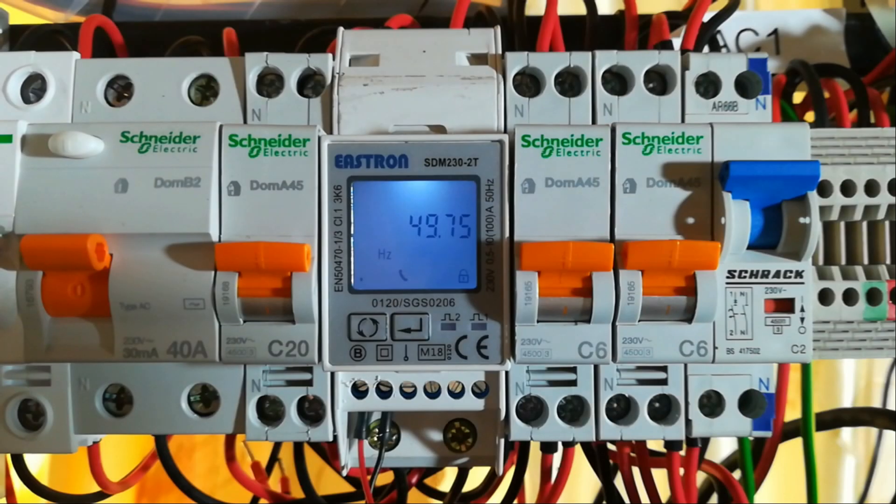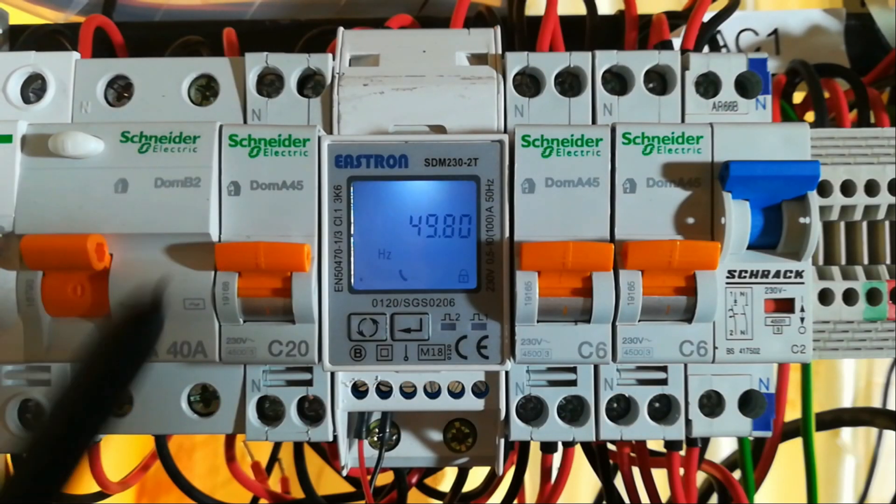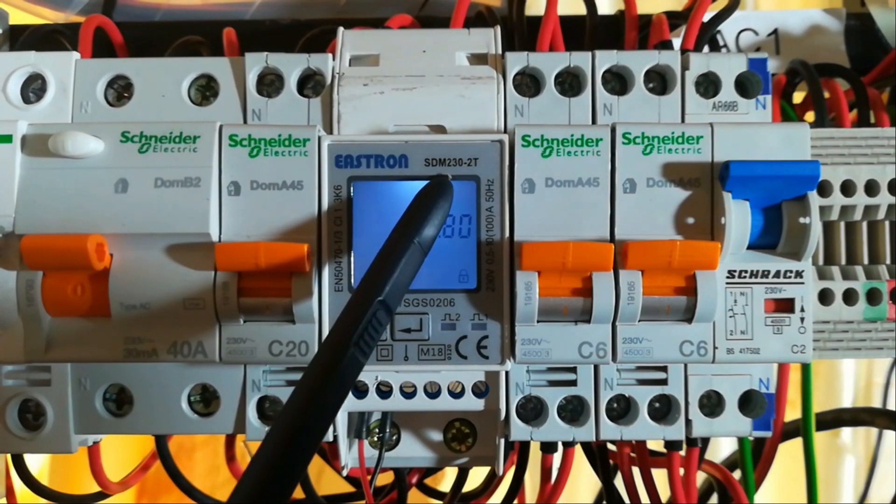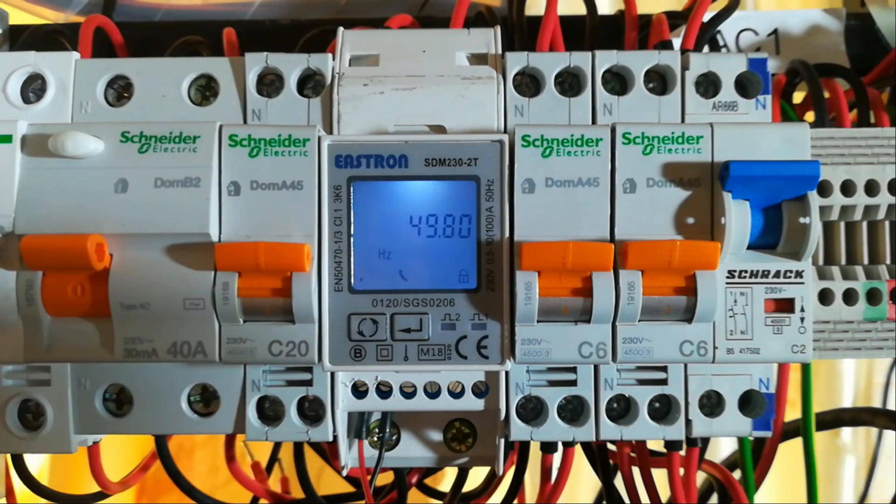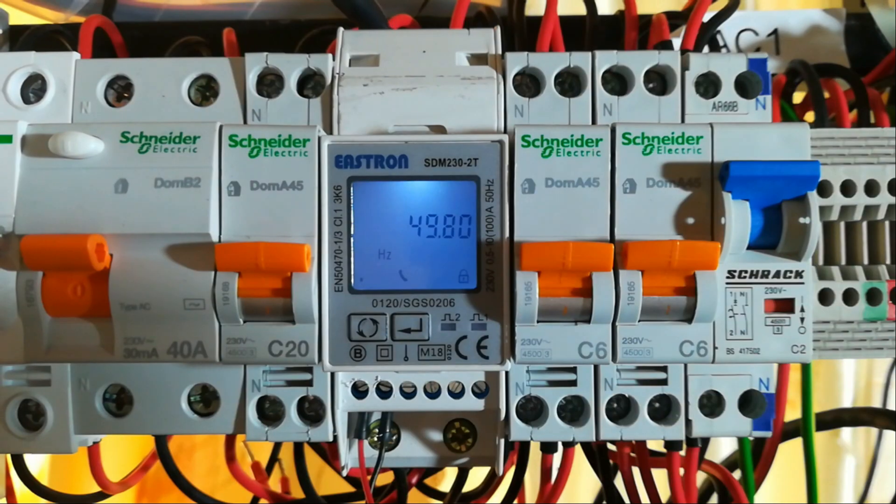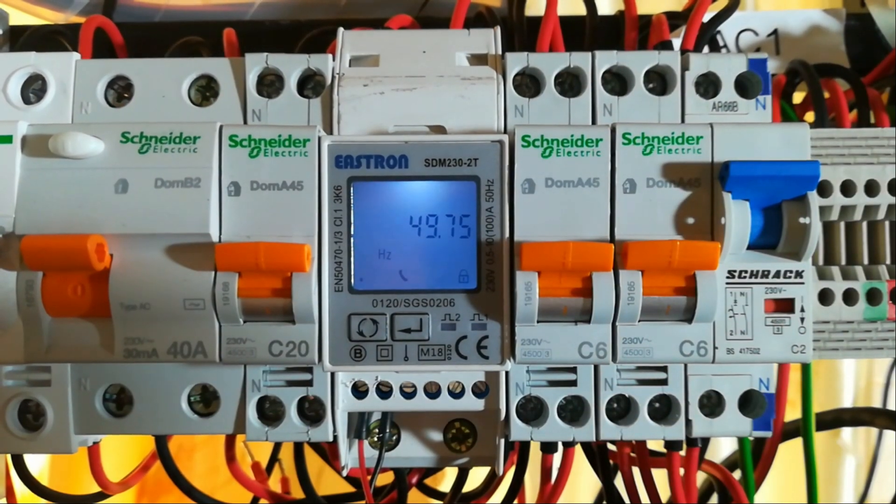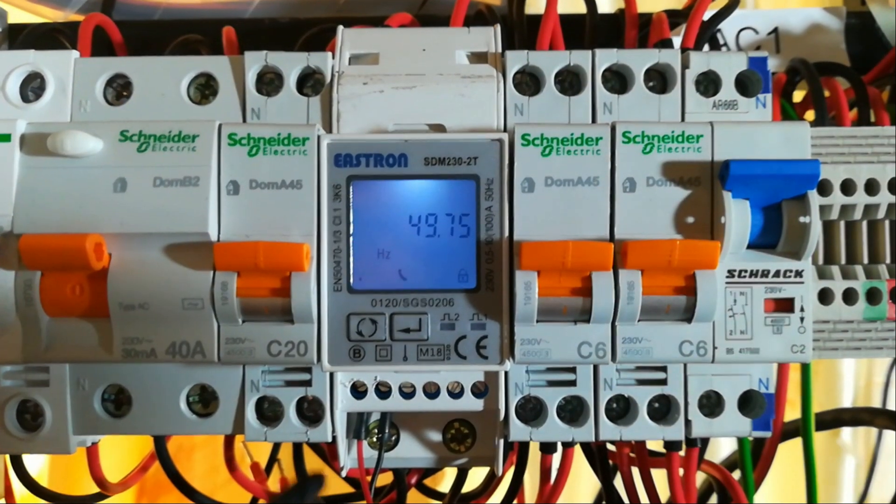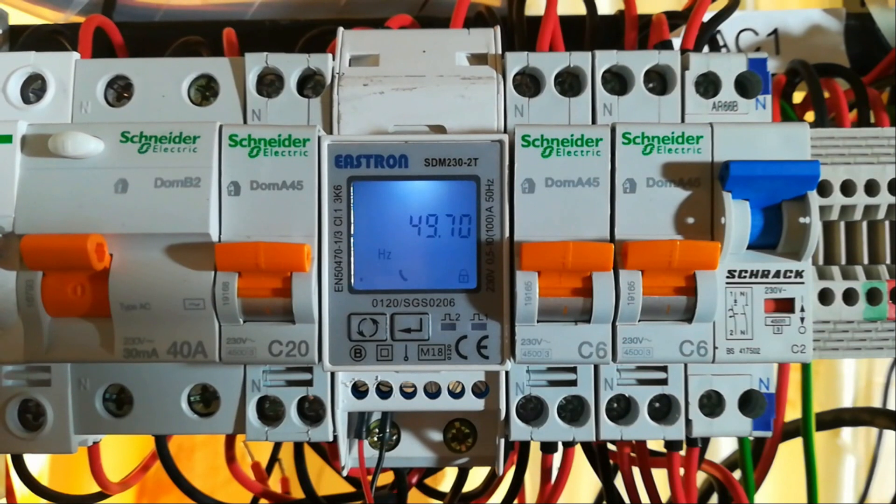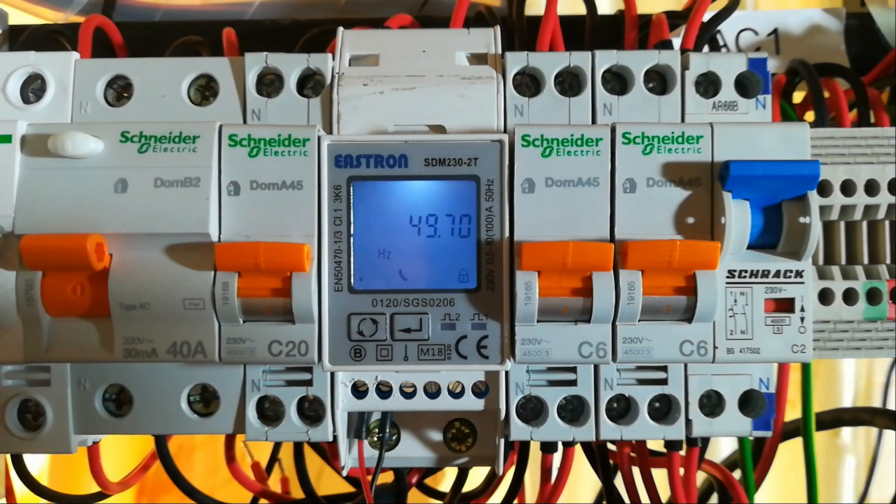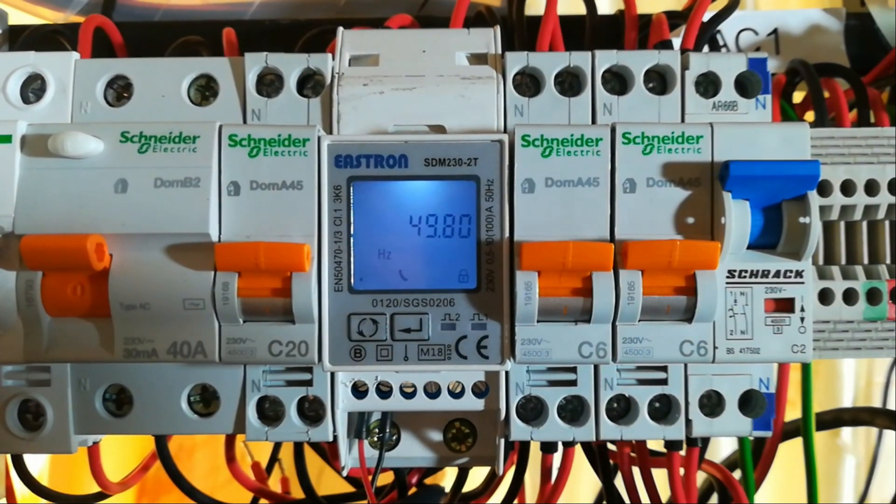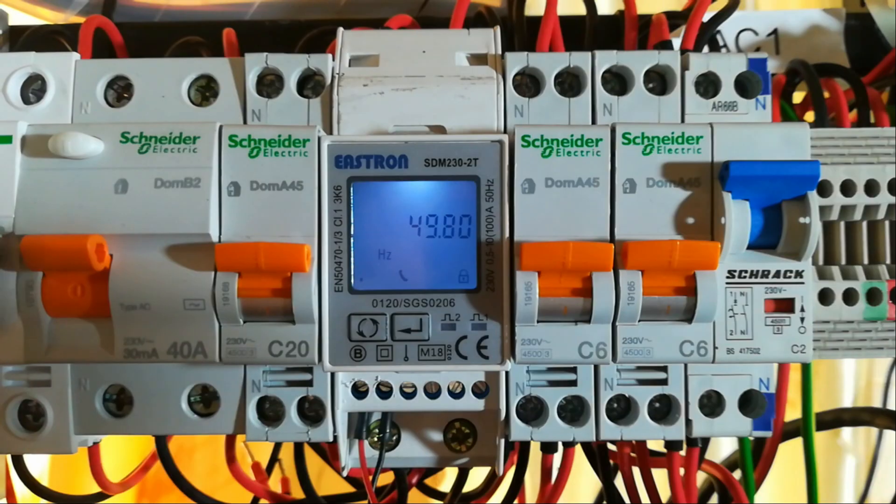First of all, this meter is from Eastron, the model number is SDM230-2T. On the top you have the incoming power that is live, and on the bottom here you have the neutral wire which is here, the black one, and this one is going in and this one is going out.